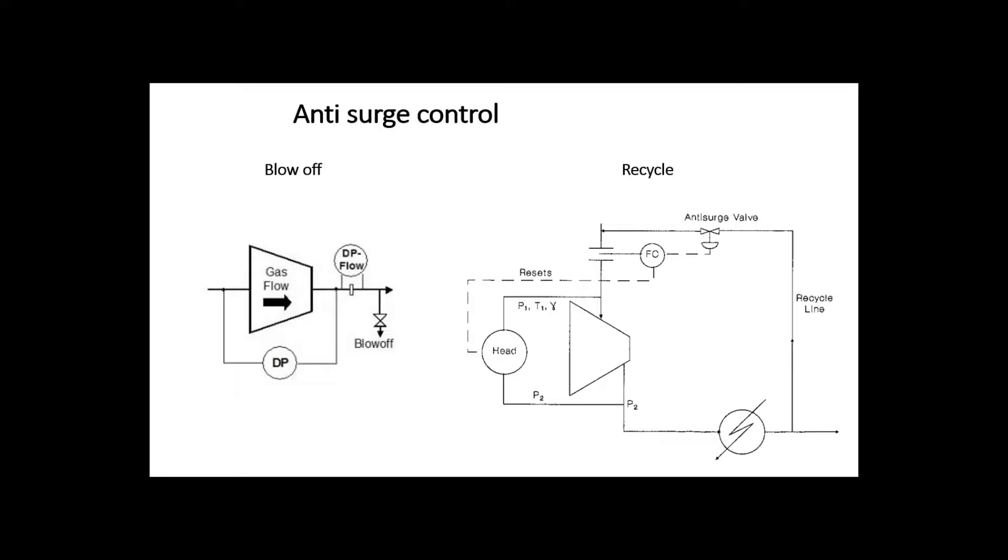But as blowing off is wasting expensive process fluid, mostly recycling is preferred and carried out through a recycle line, also called anti-surge line, with an installed anti-surge control valve on it.